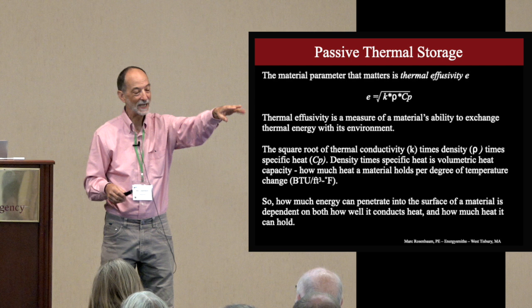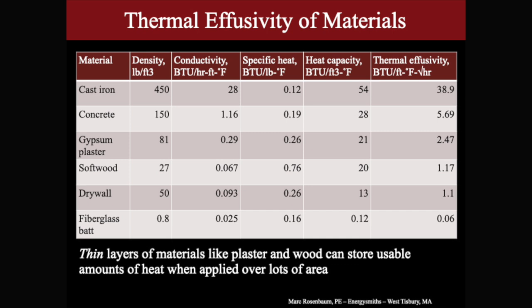Let's look at a table of thermal effusivity of materials. Cast iron is really dense, 450 pounds per cubic foot. It has great conductivity, not very good specific heat, but the other things make up for it—heat capacity of 54 BTUs per cubic foot per degree F. Its thermal effusivity is 38.9, not 39.0, not 38.8. Decimal points are very important in these things.